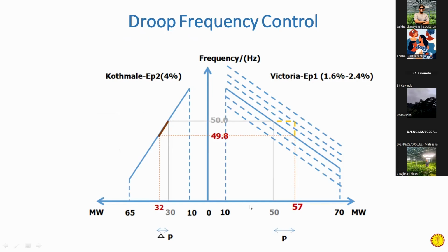This x-axis shows the power. Actually, this power is the mechanical power. So this droop setting is actually for the governor. What is its real meaning? For example, if the frequency drops from 50 hertz to 49.8, there's a 0.2 hertz drop. Now in the Victoria Power Station, it tells the governor to increase the mechanical power by 7. Earlier it is at 50, now it is at 57. The difference is how much? 7 megawatt. So this will tell its governor to increase by 7 megawatt.